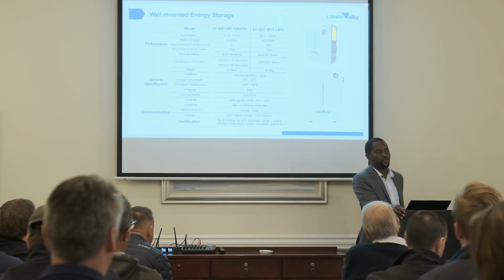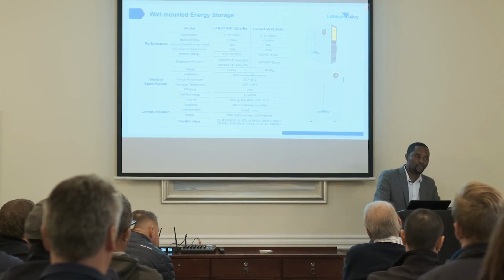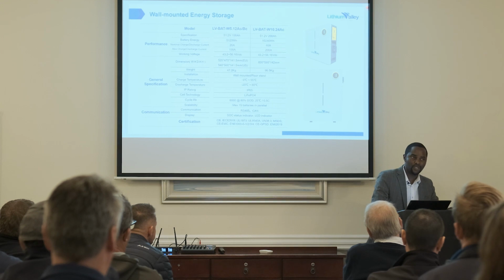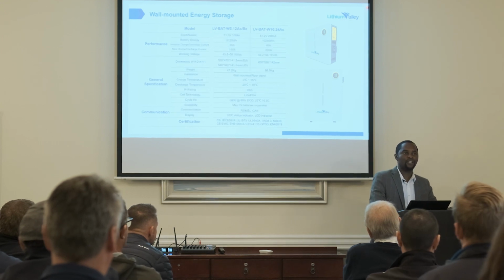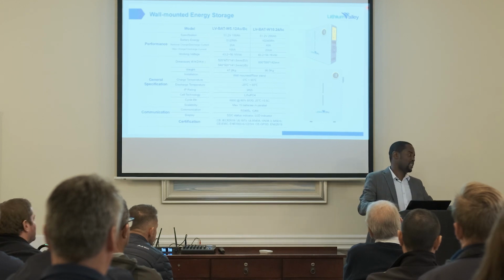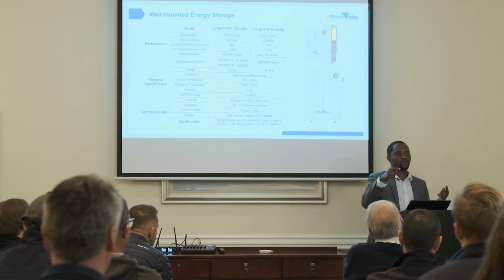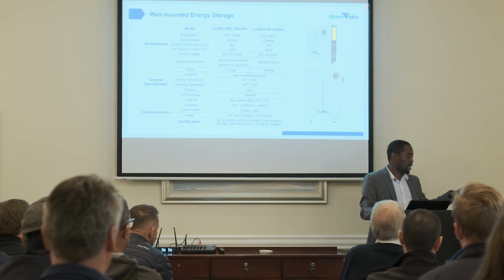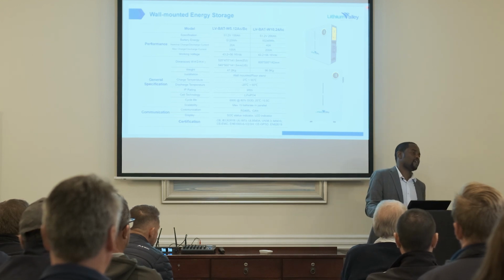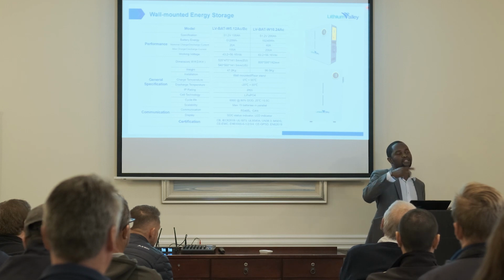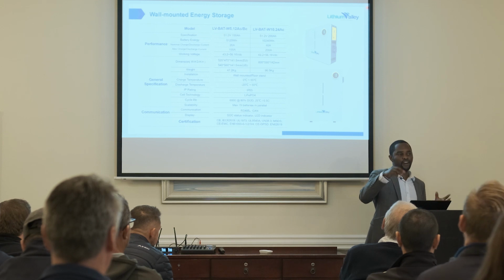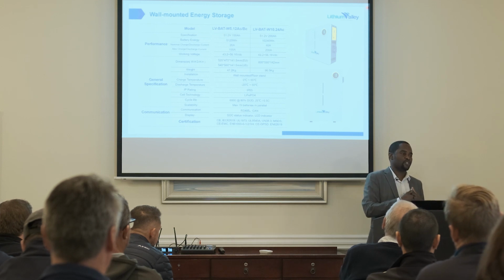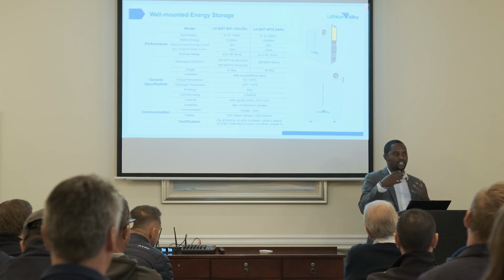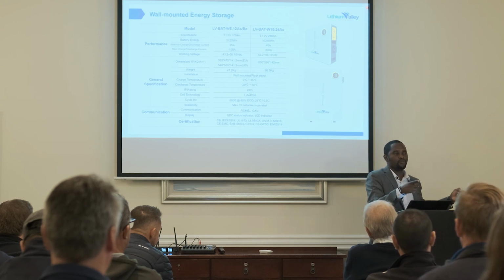So you need to change dip switches when you're buying a Greenrich battery. The ones that we're selling, not talking bad on them, but just doing a comparison. If you buy a Greenrich, you need to set the dip switches accordingly. But if you buy this, you don't need to set any dip switches because it does it automatically. What it means is you just come and switch on your master pack. Then the master pack, when it's on, it will start searching for the slaves. Then when it finds the slave, it switches it on. So when it finds and switches it on, it's peace of mind for you as an installer because you know this now has been on. I did not switch it on, which means there's already communication between the batteries.